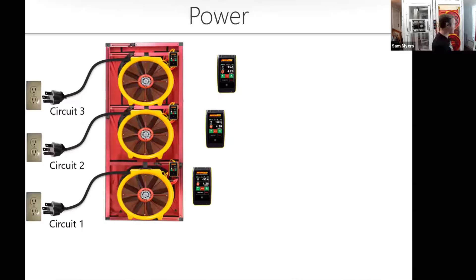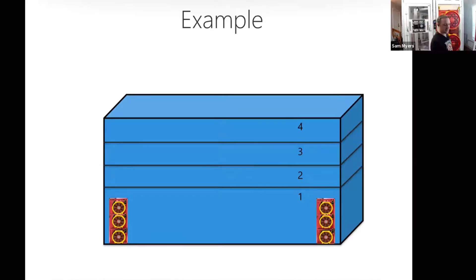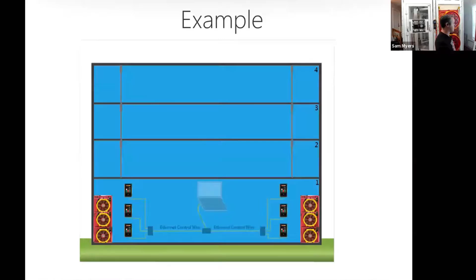And so I mentioned earlier that you want to get reference tubes to each floor to make sure that the entire part of the building is going to be under that desired pressure that you're testing to. So if you're testing to 50 pascals, you want to make sure you have tubing up there to reference the top if your fans are at the bottom, to make sure that that building is getting a universal pressure all the way through it.